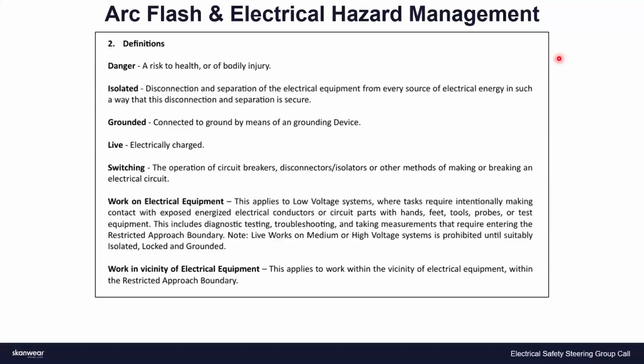So I know we've struggled with using low, medium, high voltage, and it also depends on if you're using NEC versus NFPA 70E. So I'd prefer that whenever you're writing these types of things, you're actually calling out the voltage there if you can, or if you need to define your voltages in another definition, you can do that. But it gets really complicated when you're talking low to medium to high, depending on where you're located. Agreed.